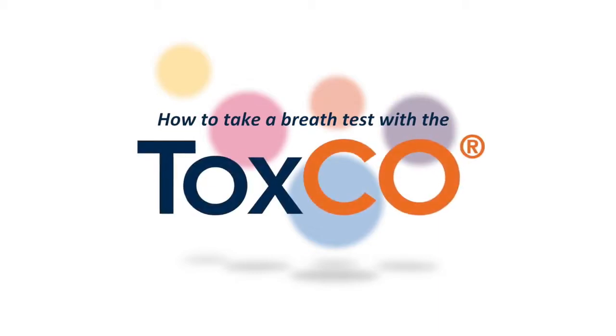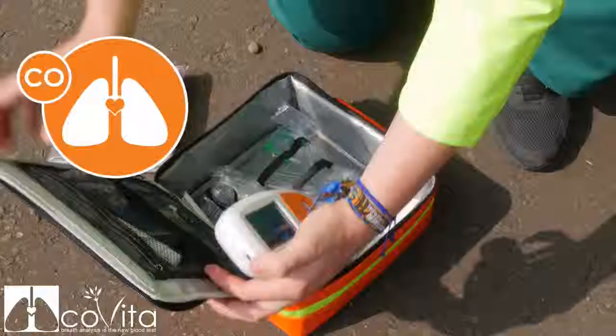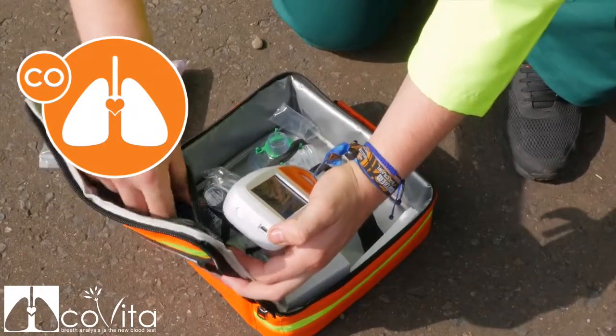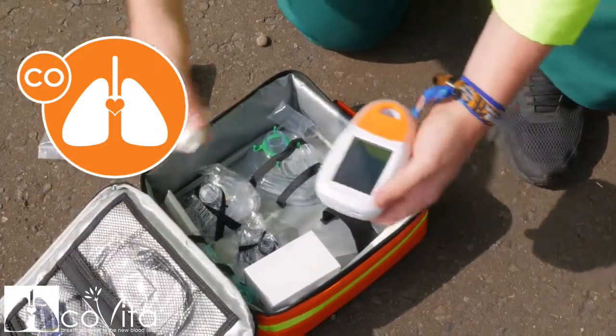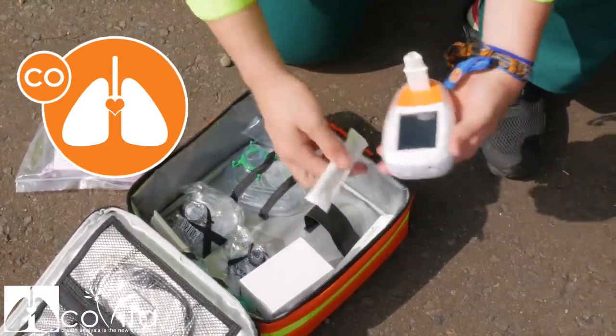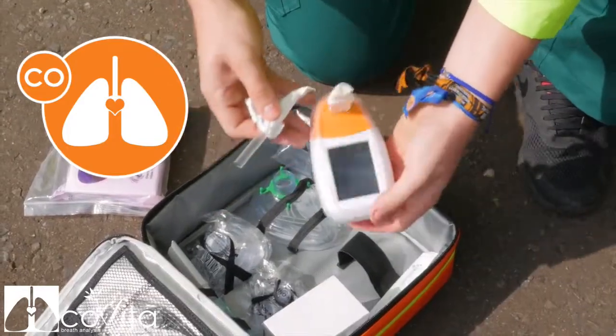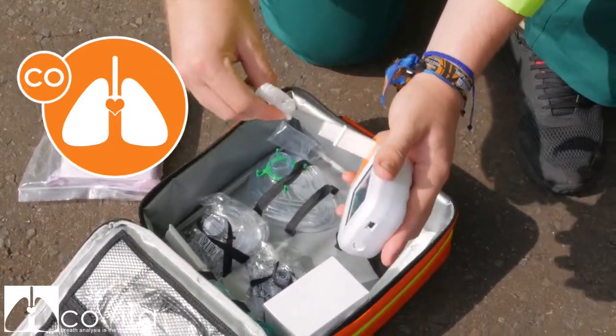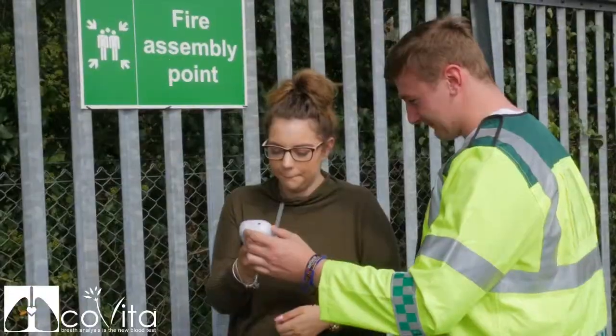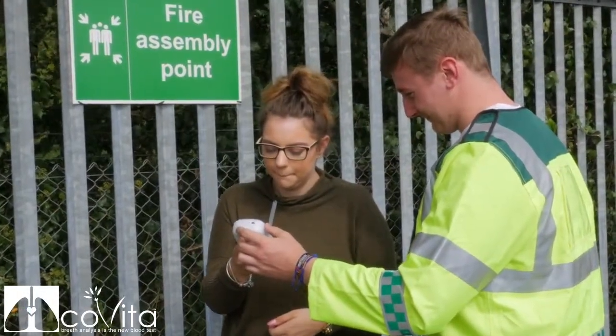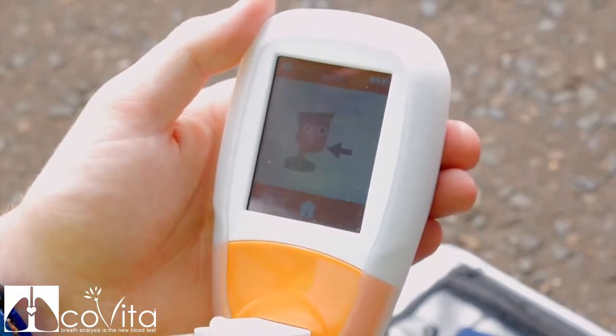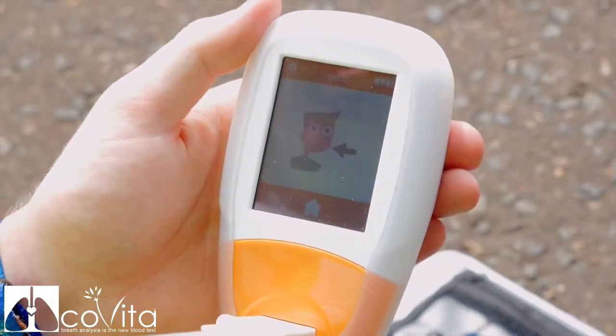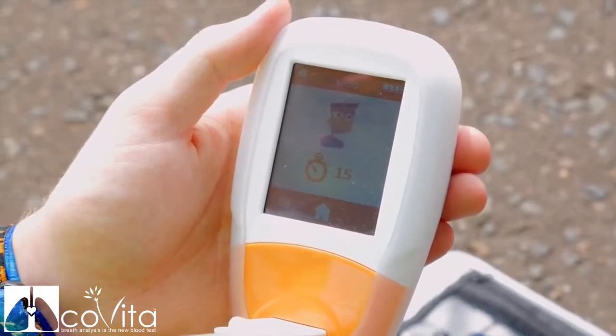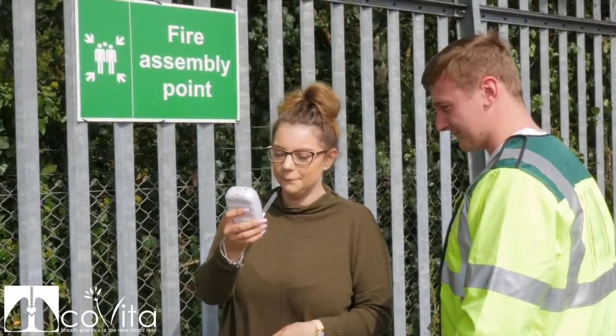To take a mouthpiece breath test with the ToxCO, first attach the D-piece to the ToxCO and then the SteriBreath to the D-piece. Click on the mouthpiece breath test icon to begin. You will be asked to inhale and hold your breath for the preset 15-second countdown before slowly blowing into the ToxCO.